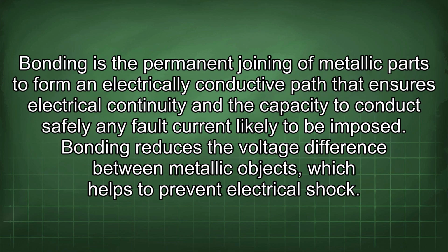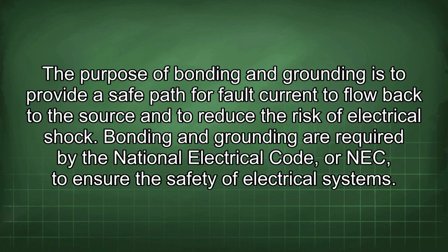Bonding is the permanent joining of metallic parts to form an electrically conductive path that ensures electrical continuity and the capacity to conduct safely any fault current likely to be imposed. Bonding reduces the voltage difference between metallic objects, which helps to prevent electrical shock. The purpose of bonding and grounding is to provide a safe path for fault current to flow back to the source and to reduce the risk of electrical shock.